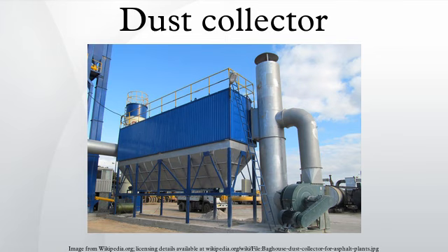Unit collectors. Unlike central collectors, unit collectors control contamination at its source. They are small and self-contained, consisting of a fan and some form of dust collector. They are suitable for isolated, portable, or frequently moved dust-producing operations, such as bins and silos or remote belt conveyor transfer points. Advantages of unit collectors include small space requirements, the return of collected dust to main material flow, and low initial cost. However, their dust holding and storage capacities, servicing facilities, and maintenance periods have been sacrificed.